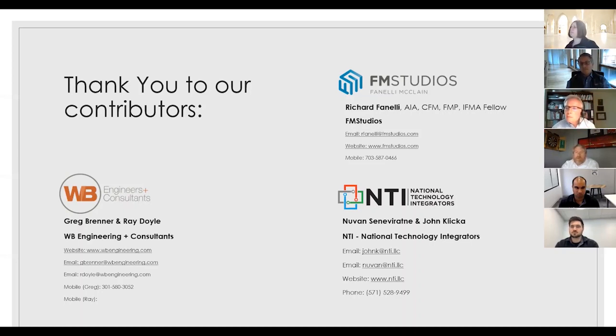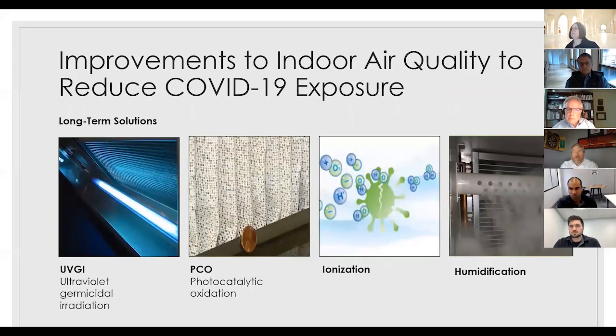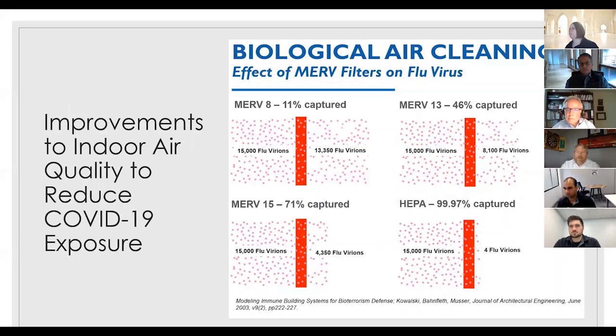I'd highly recommend doing the same thing on the filtration side. Many houses don't have outside air ducts connected, but when it's nice out, you should open a window or two for cross ventilation, that's healthy. At minimum, increase your filtration rating. The real issue with filtration is that one filter rating to the next can mean a pressure drop of another tenth of an inch of water pressure. In simple terms, if you normally change your filter every 4 to 6 months, moving to the next filter classification means you'll need to change it twice as often. But looking at the slide we had earlier, that's roughly a 40%, or 4x, difference in filtration between a MERV 8 and a MERV 13, a huge difference in particles reduced and capture rate. The cost of changing your filter every 3 months instead of every 6, in my opinion, is well worth it.